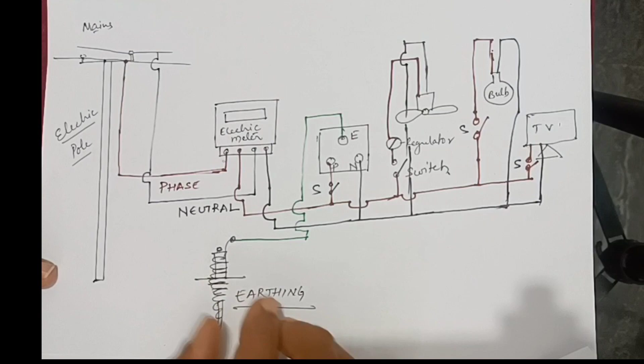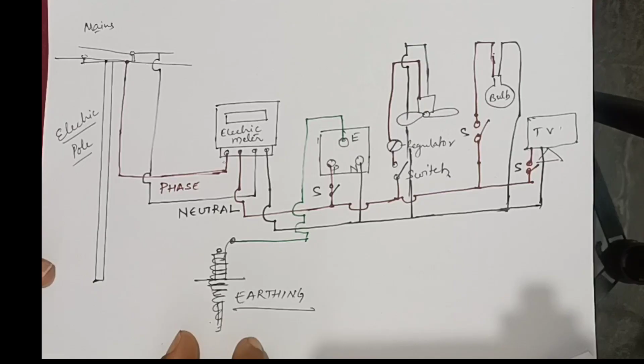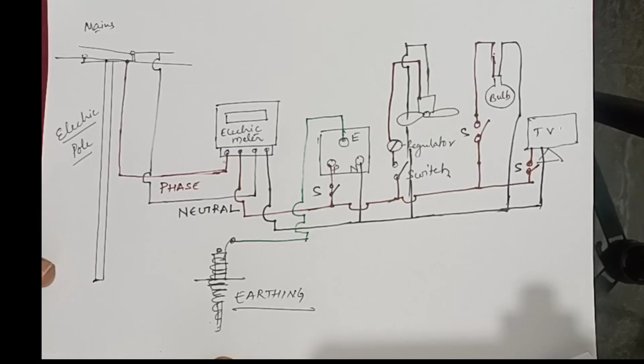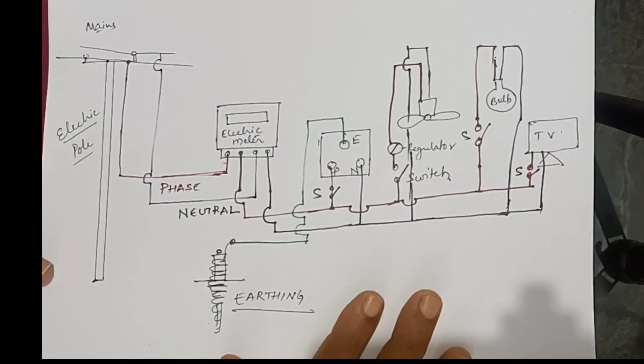This is how earthing is taken outside the house, where we will do earthing through an iron pipe or aluminum pipe, wound with a copper wire, inserted deep inside the earth for proper earthing, with charcoal, salt and everything poured inside, so that we get a proper earthing, and it should be a little wet so that proper earthing is made deep inside. So this is connected to the earthing point wherever the earthing is needed. So this is how the house wiring is done.